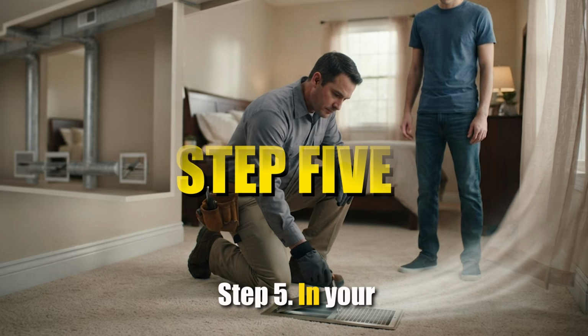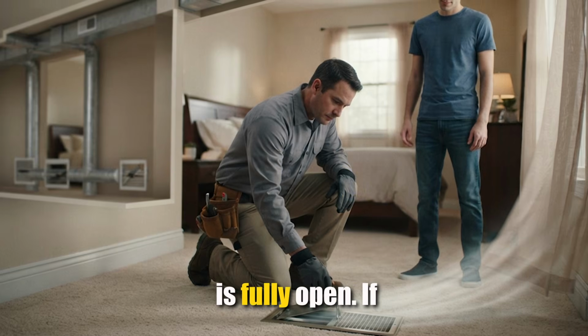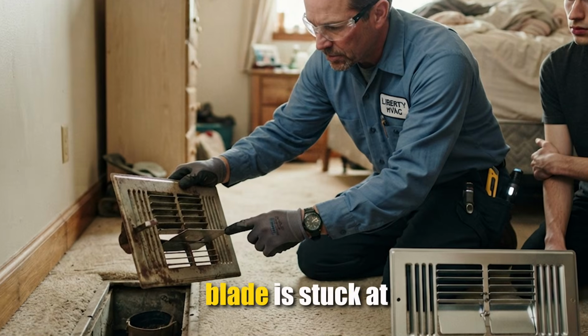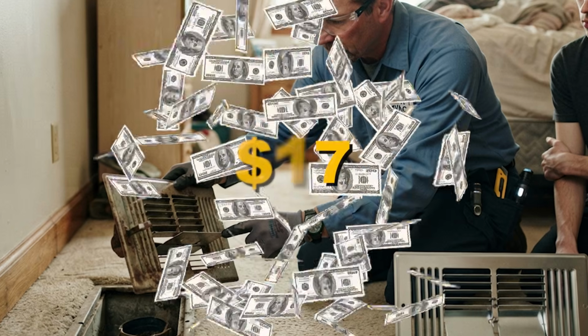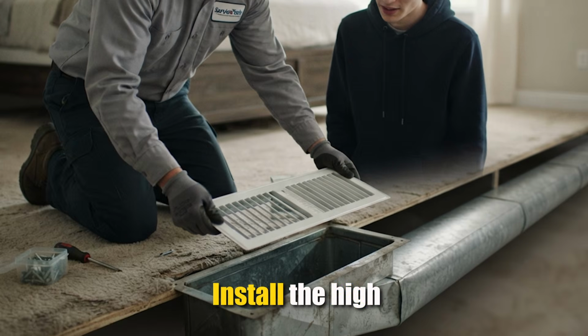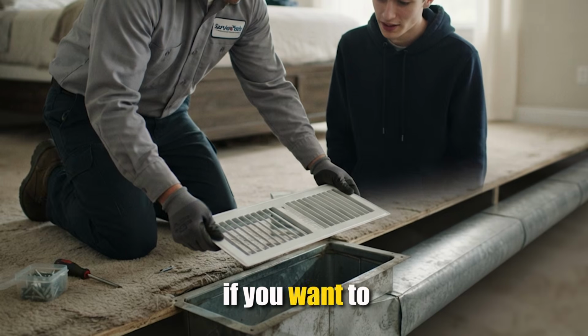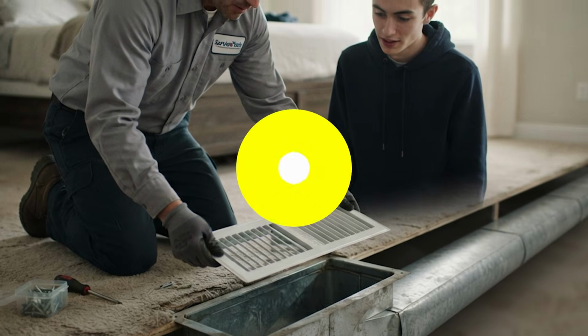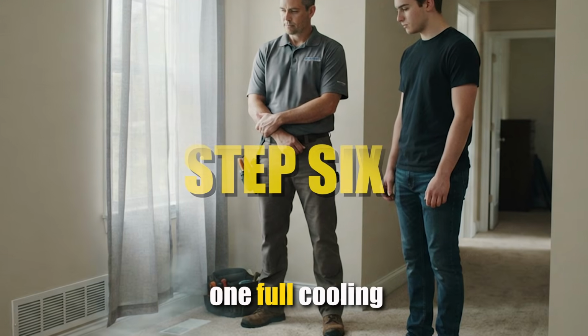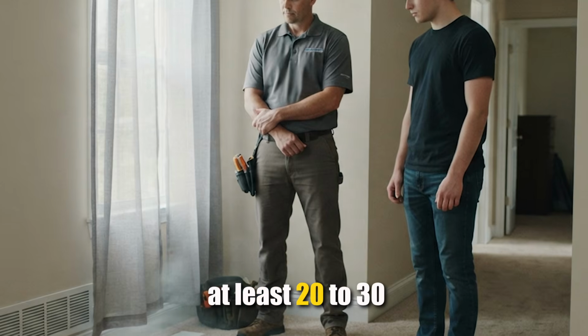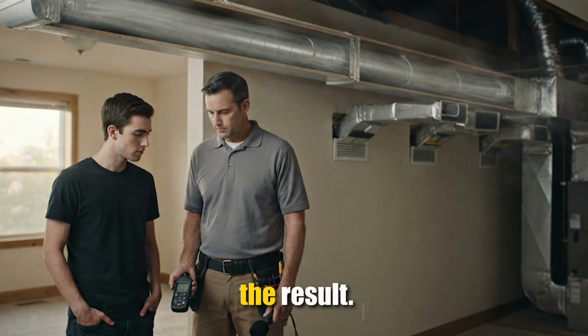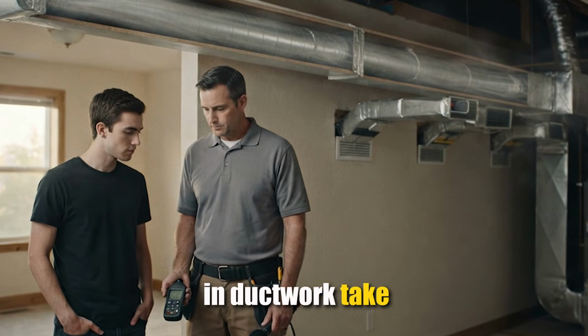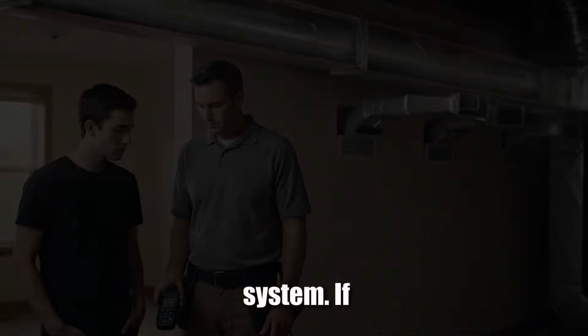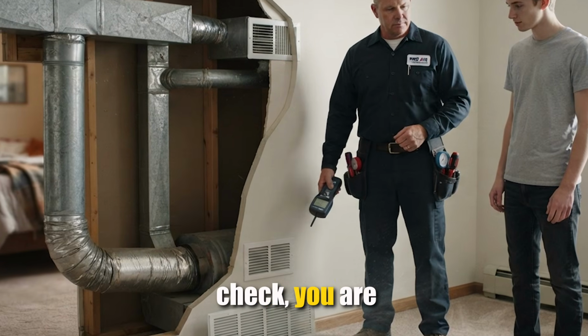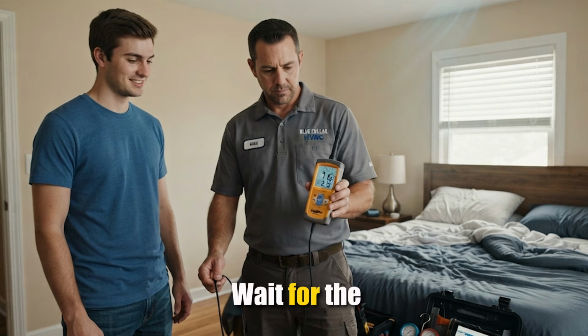Step 5. In your hot room, make sure the register is fully open. If the damper is broken and the blade is stuck at anything less than fully open, that is your $17 replacement. Install the high-flow version here if you want to maximize delivery to this specific room. Step 6. Wait one full cooling or heating cycle, at least 20 to 30 minutes, before you evaluate the result. Pressure changes in ductwork take time to propagate through the whole system. If you adjust and immediately check, you are not seeing the real outcome. Wait for the system to settle, then measure temperatures again.